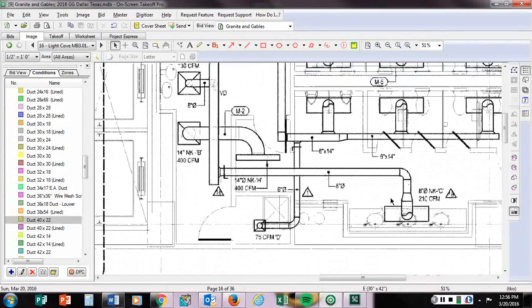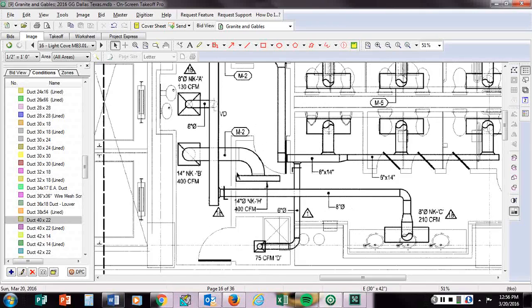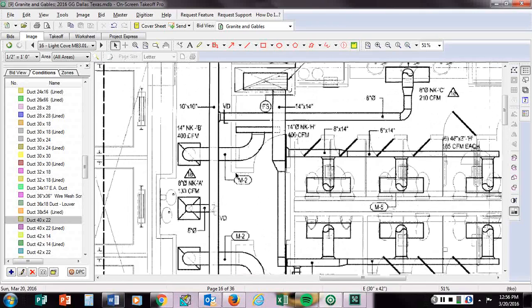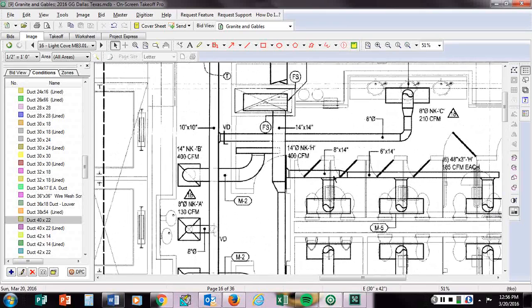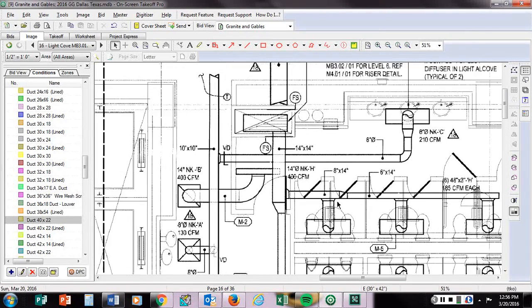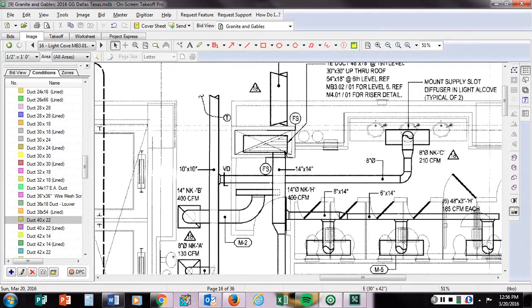You can see here we have some exhaust, and the exhaust does not have to be insulated. As we come across, these are all 185 CFM apiece. Each one I'd run an 8-inch duct out to it since it's not specified, with a takeoff and an 8-inch duct in a 90, then put the register there. Right here is our chase that goes up for our toilet exhaust fan. Keep that in mind, we're going to get there in a few minutes.